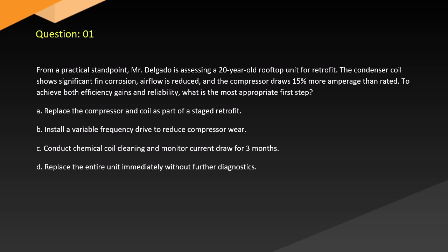Question 1. From a practical standpoint, Mr. Delgado is assessing a 20-year-old rooftop unit for retrofit. The condenser coil shows significant fin corrosion, airflow is reduced, and the compressor draws 15% more amperage than rated. To achieve both efficiency gains and reliability, what is the most appropriate first step?